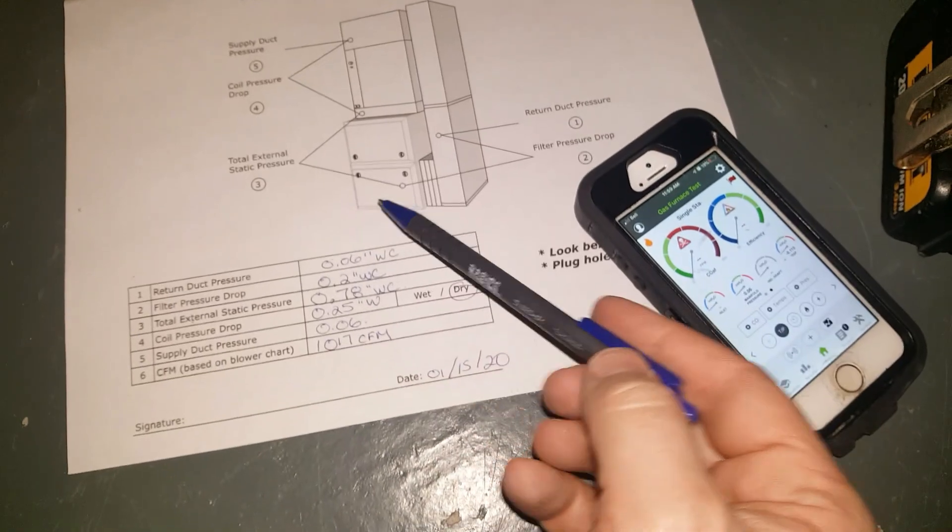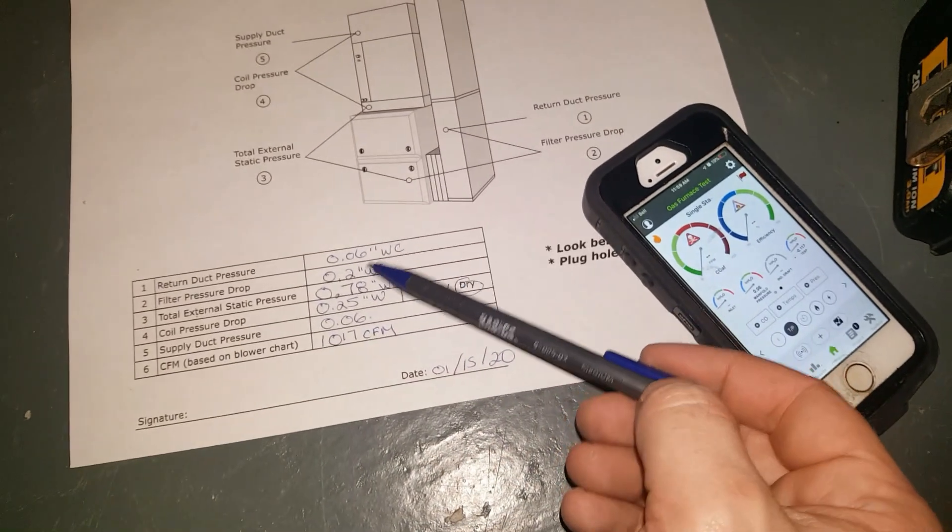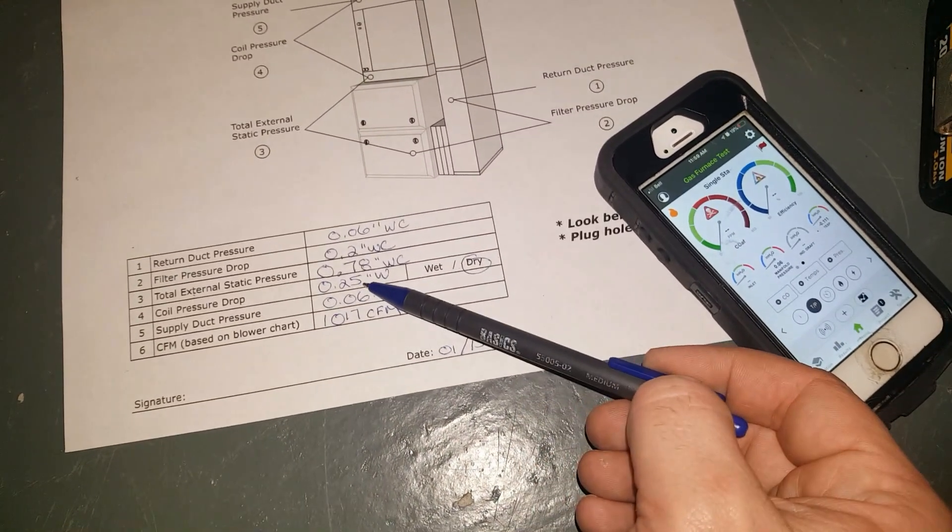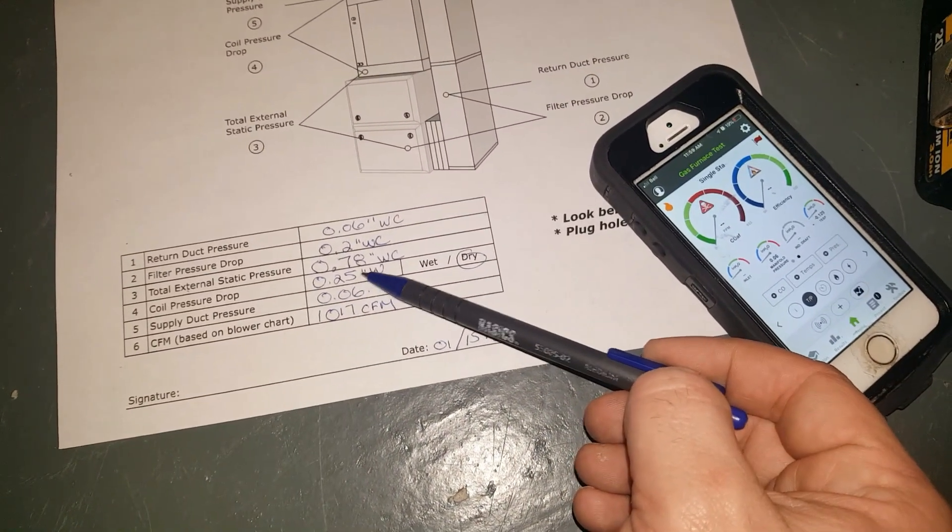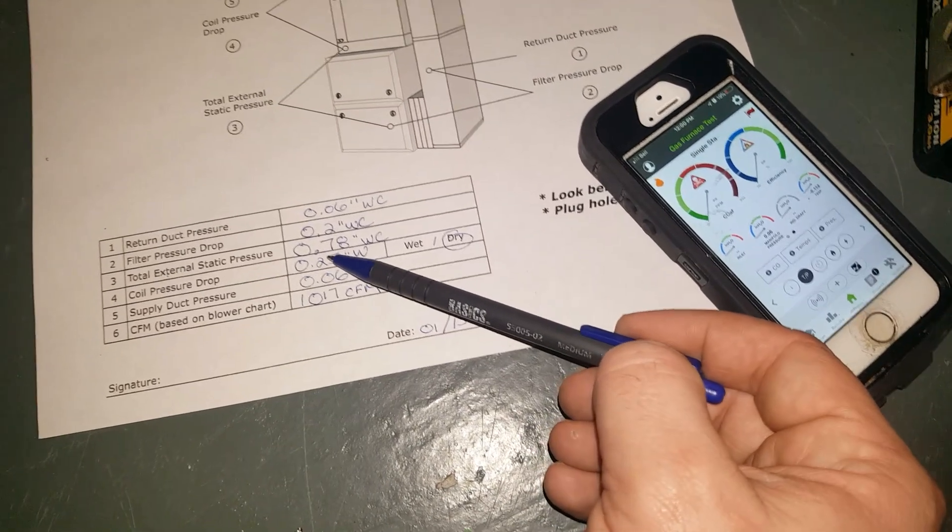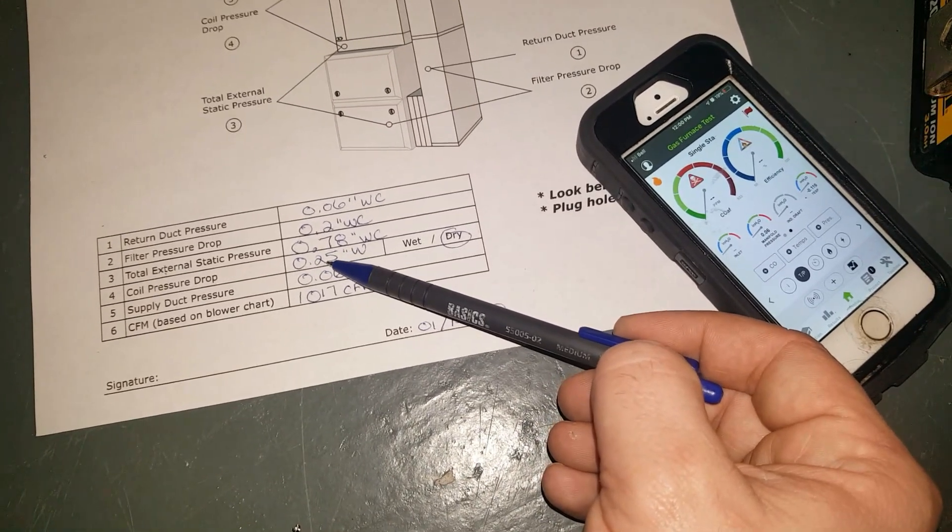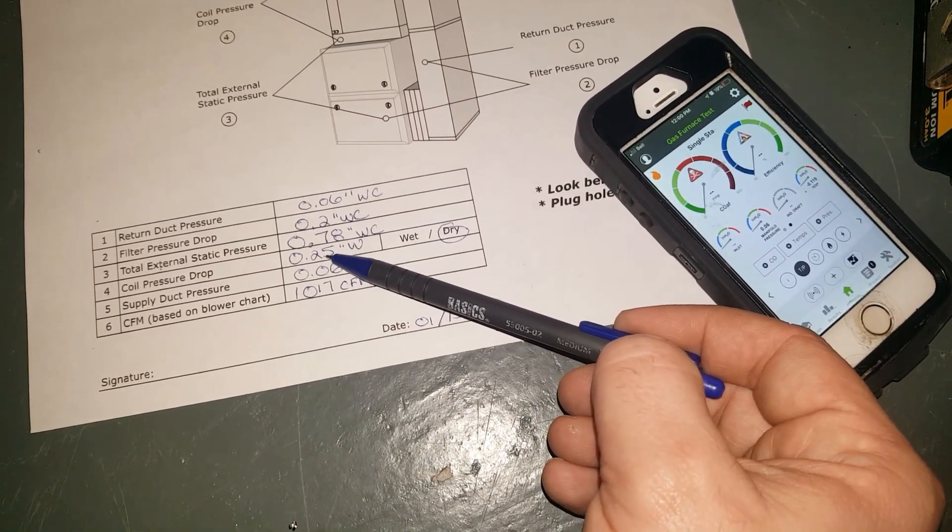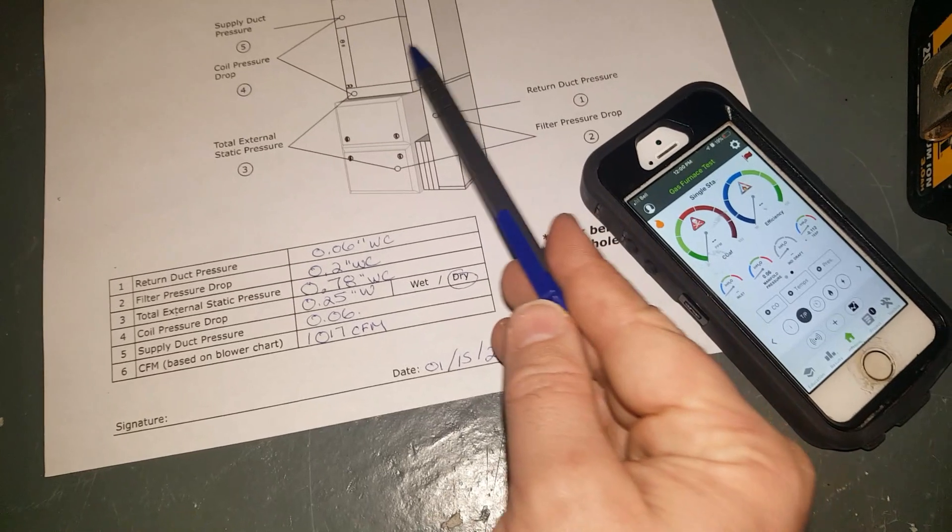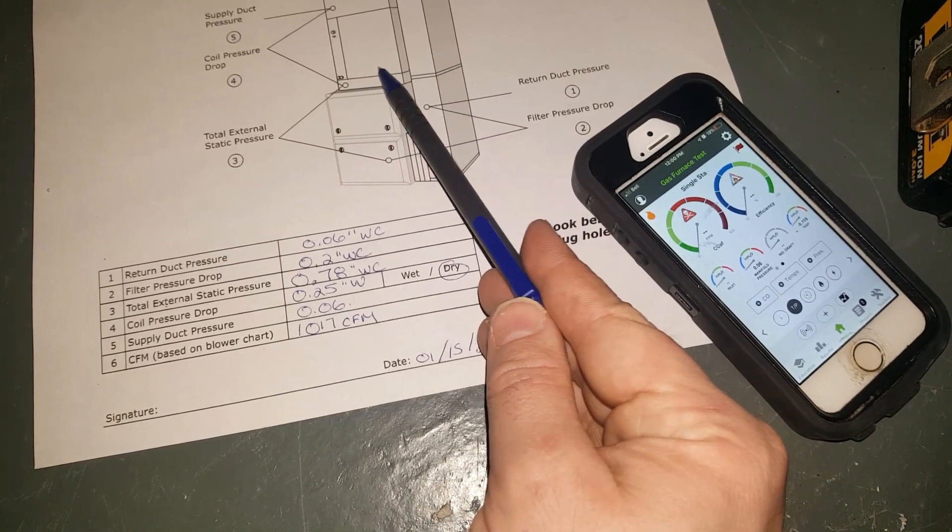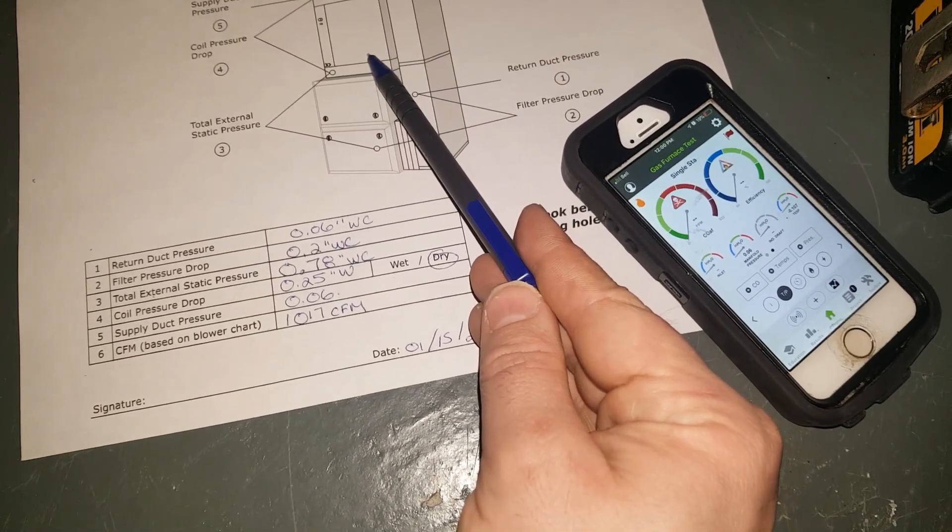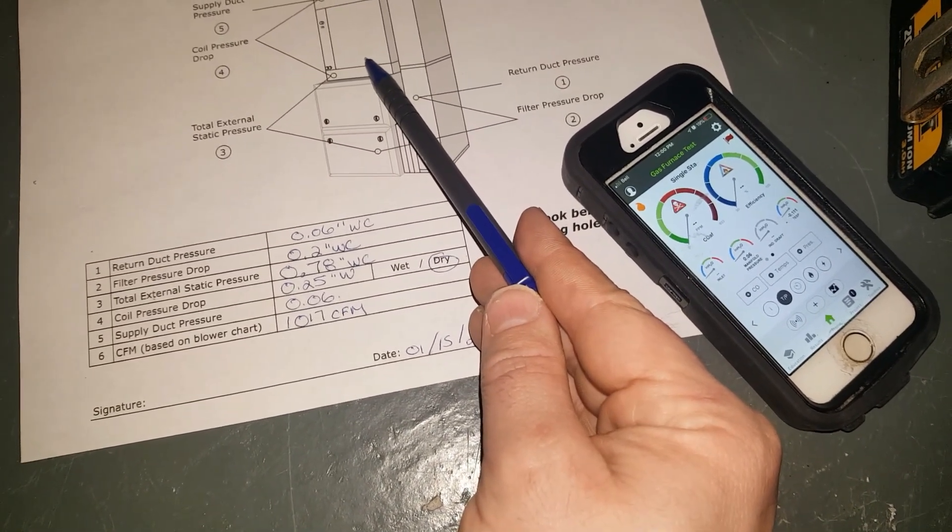And then we can start noticing issues. If this number goes up, for example coil pressure drop, say it goes 0.5, then I know my evaporator is getting dirty and we can recommend a cleaning.